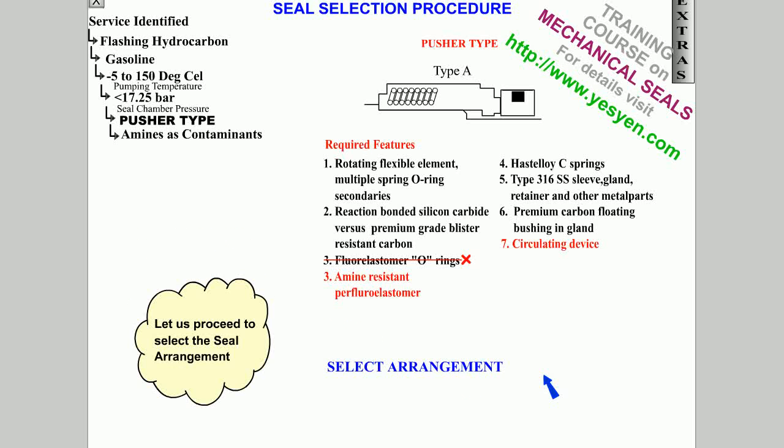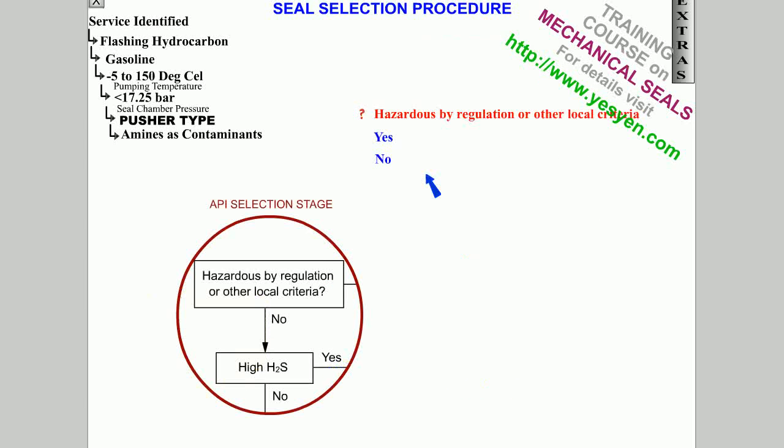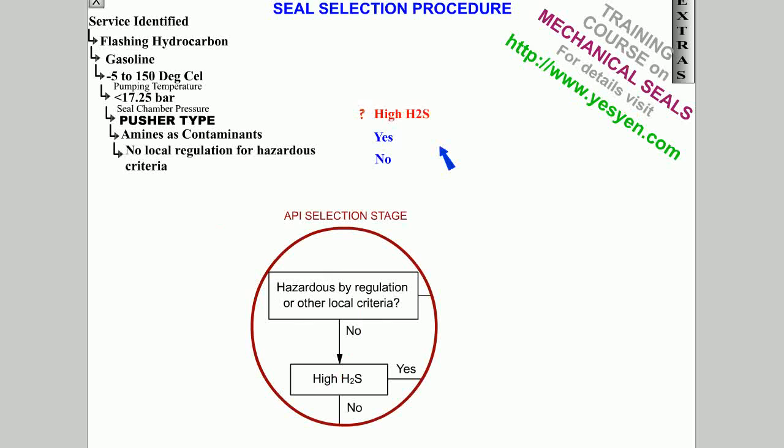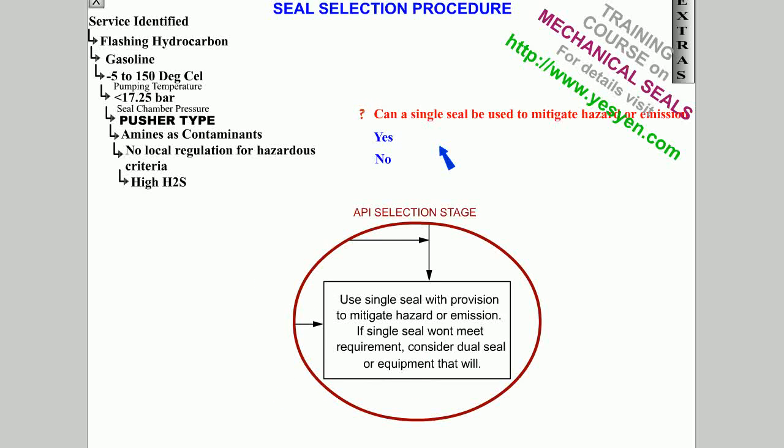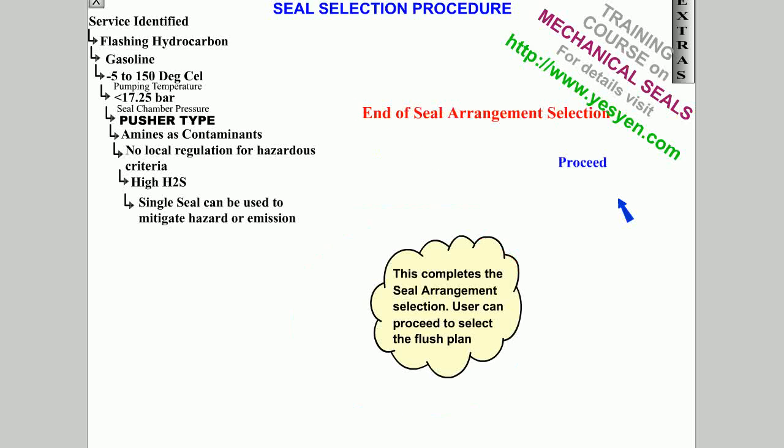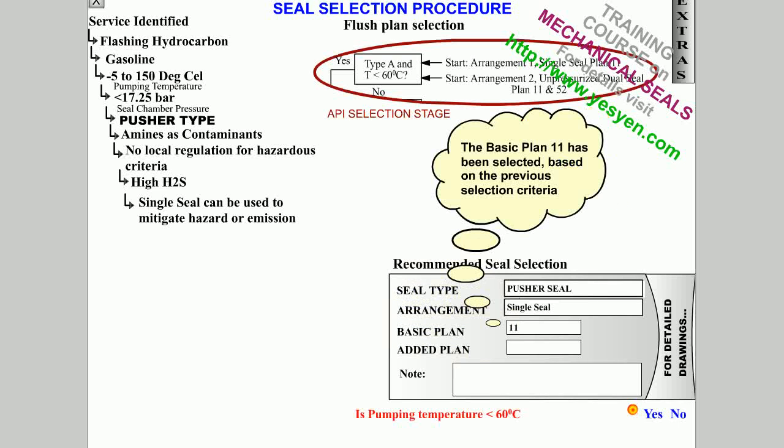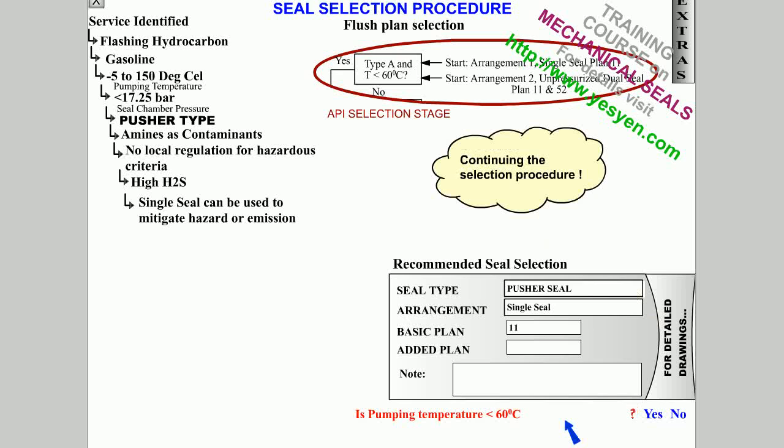Let us select the seal arrangement. This completes the seal arrangement selection. The user can proceed to select the flush plan. The basic plan 11 has been selected based on the previous selection criteria. Detailed drawings of the current stage of selection can be availed at any time. Continuing the selection procedure.